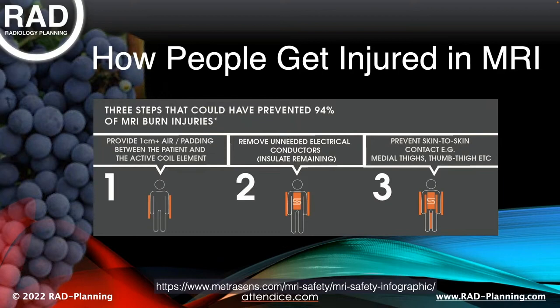This concern is particular to when the body coil is doing the transmitting, which is most MR studies. So your manufacturer will describe a minimum set standoff distance from the bore wall. And that can be 5 millimeters to a centimeter, depending on your MR system and the manufacturer's specs. The reason for that standoff distance is that the RF energy we use in MR imaging is not too dissimilar from microwaves. When you are closer to the RF transmit source, there is what's called a dipole-dipole coupling. Essentially, it's microwave excitation, microwave heating.